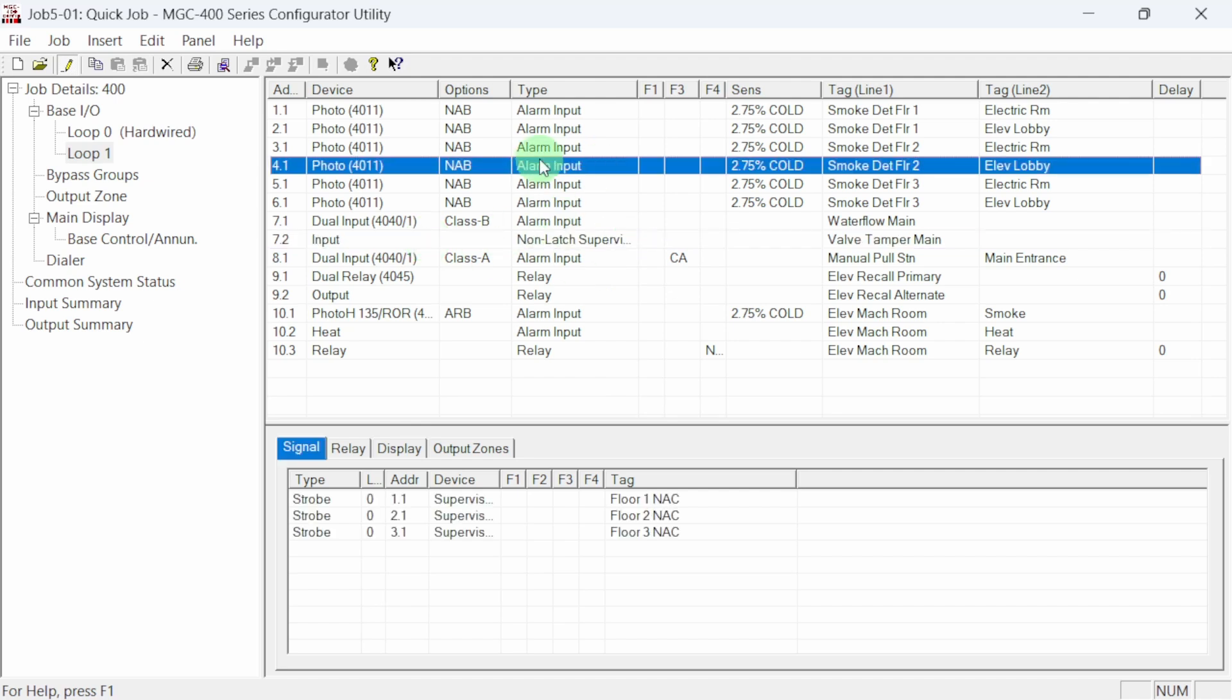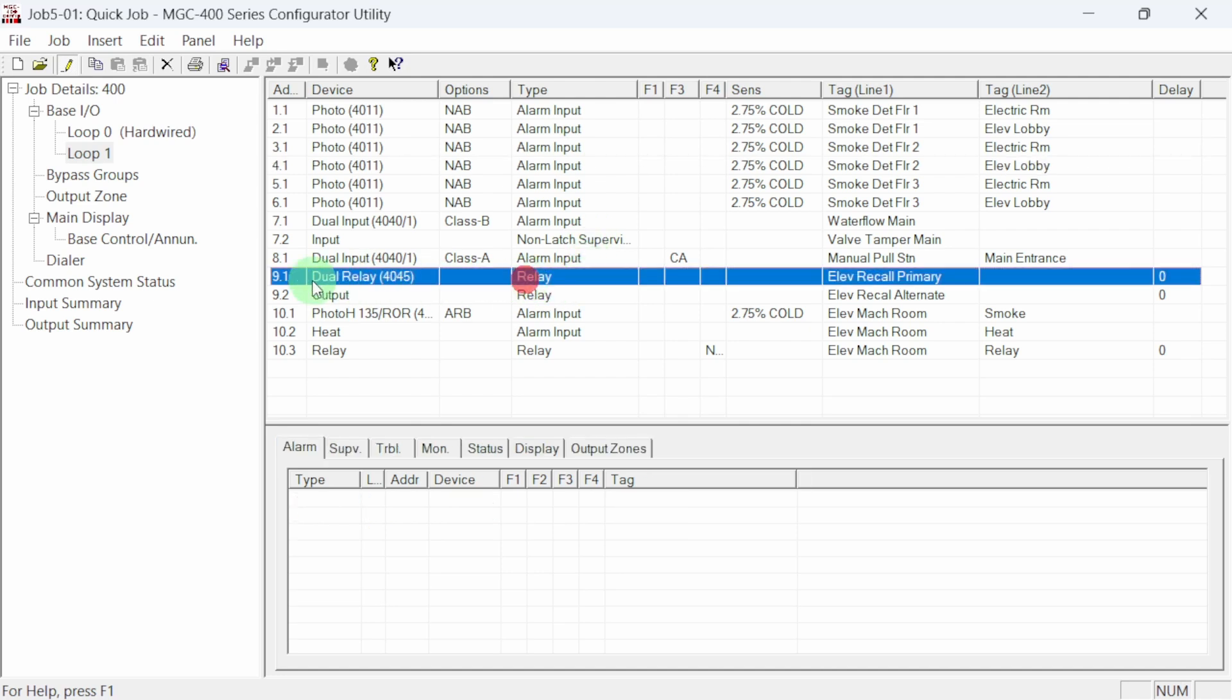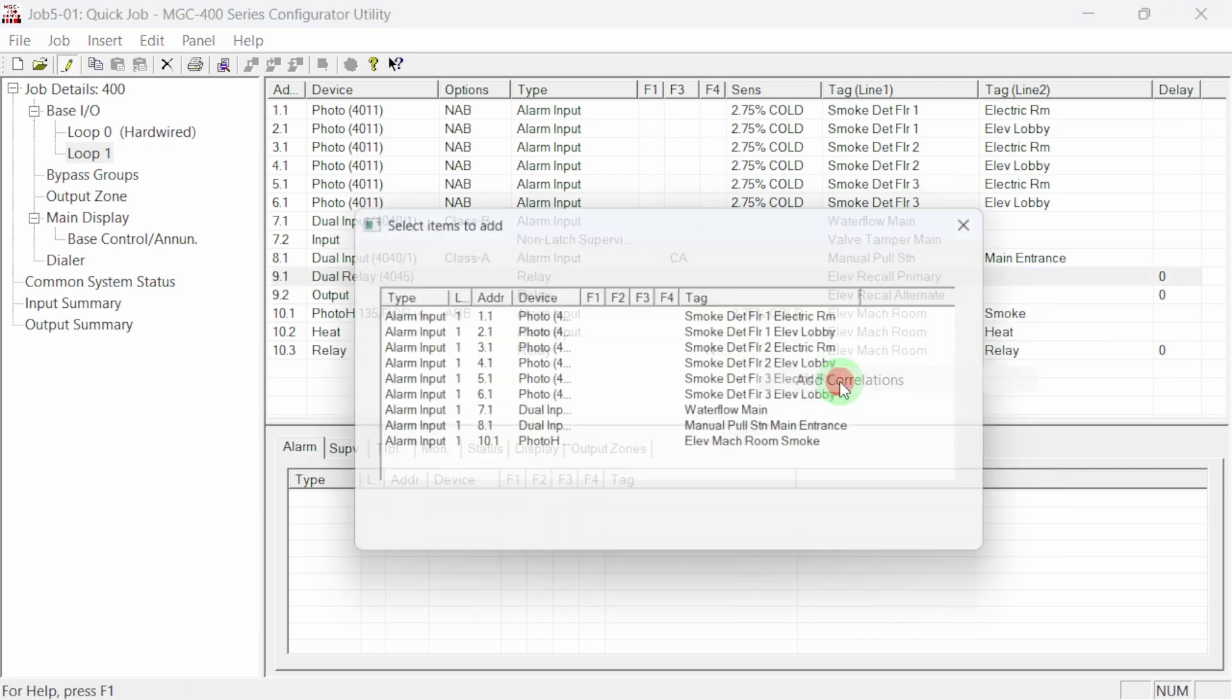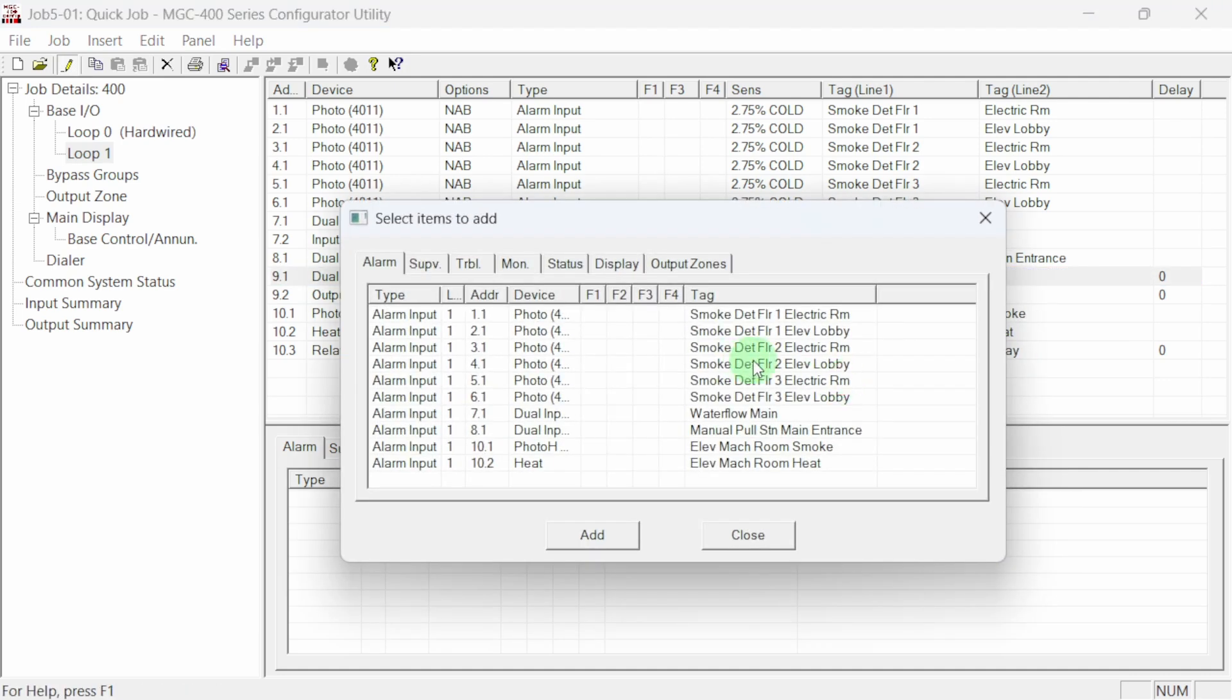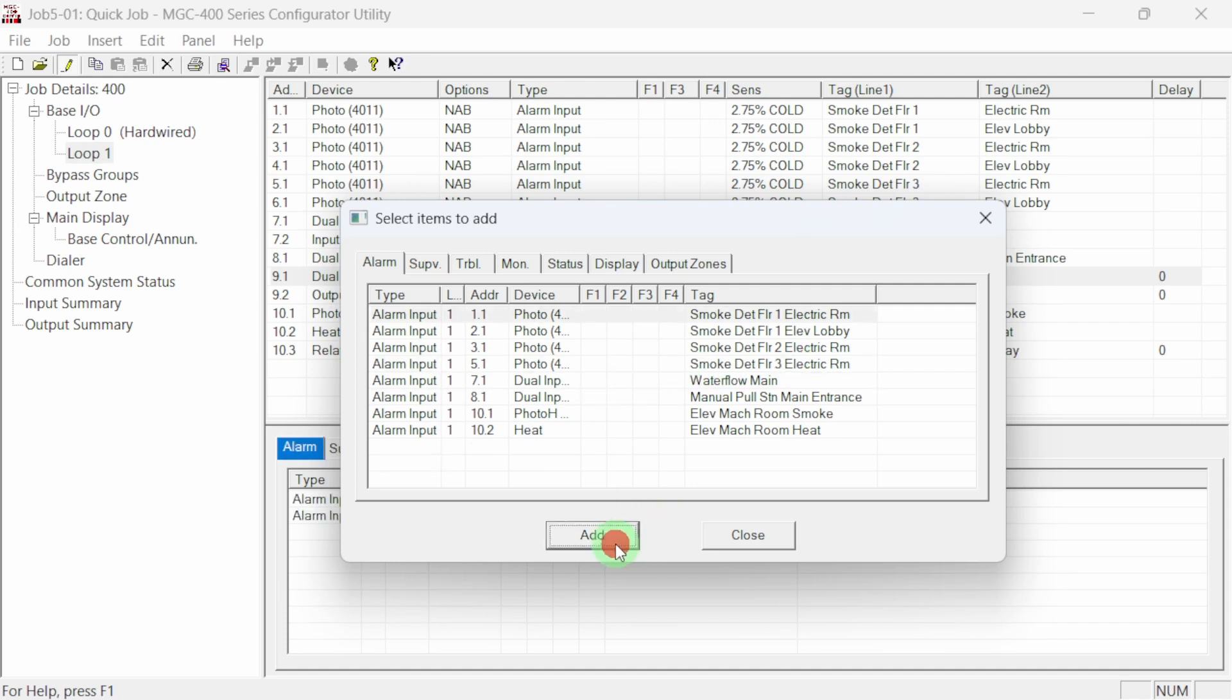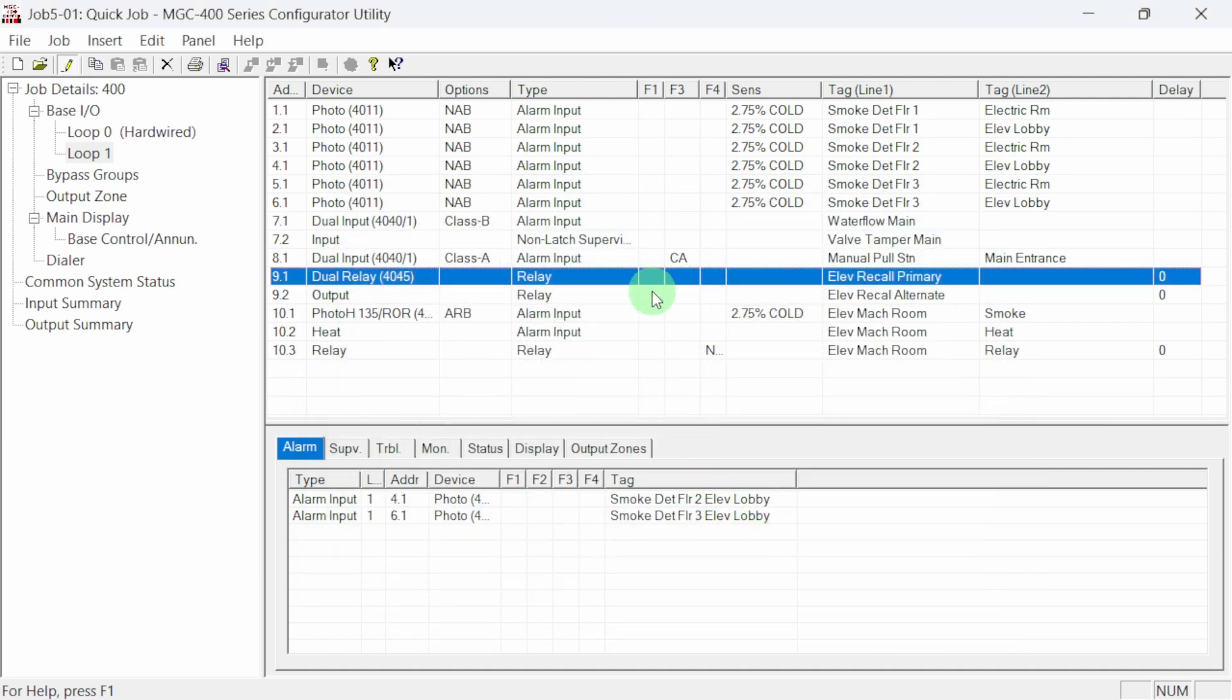We have a few more correlations to make. The primary elevator recall relay needs to be correlated to the second and third floor elevator lobby smoke detectors. To do this quickly, we can correlate these input devices directly to the primary recall relay. Right-click on the relay and select add correlations. Next, find and select the second and third floor elevator lobby smoke detectors and add them to the relay. The two elevator lobby smoke detectors have now been correlated to the primary recall relay.